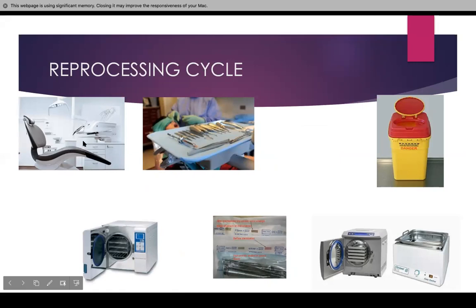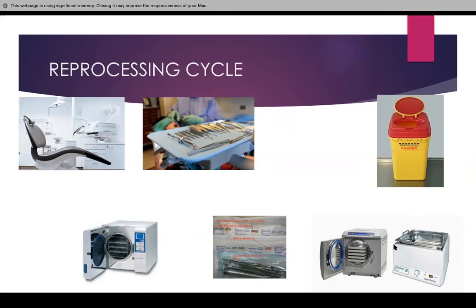We are going to have the point of care, and then the transportation. For transportation to the reprocessing area, it has to be in a closed container so that no sharp injuries can occur. Anything that is sharp is going to be placed in something like this, and then you're going to have the pre-cleaning with the ultrasonic or just washing, and then the ultrasonic. You're going to have the drying with a lint-free cloth.